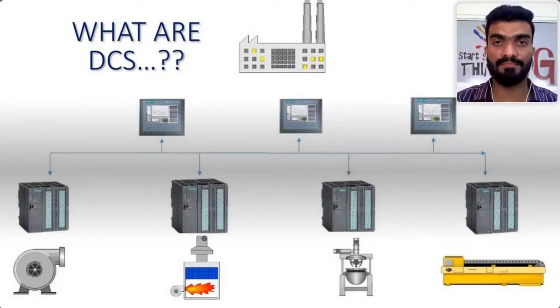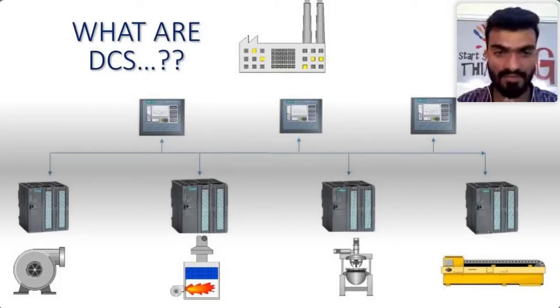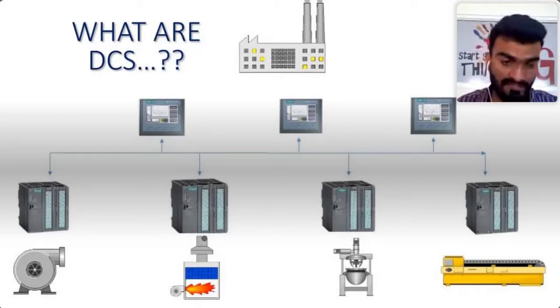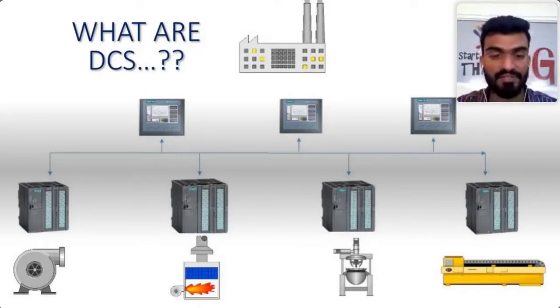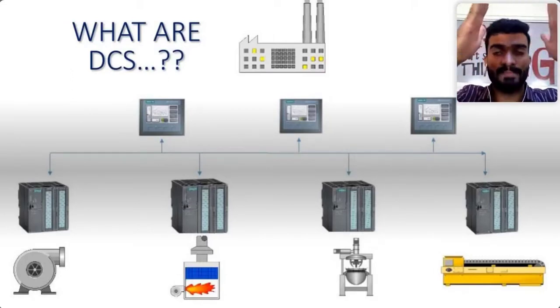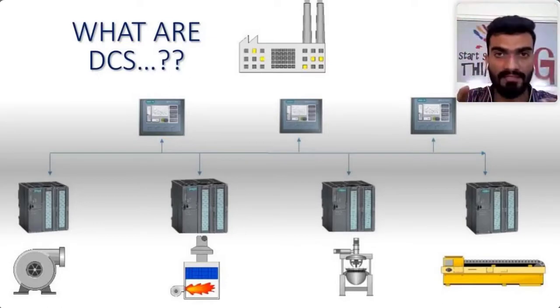In this slide we've shown three controllers, and the main distributed controls are all the bottom PLCs, second-line PLCs at different sections - say fans, furnace, machine conveyors - all these different kinds of PLCs at different sections are connected to the DCS. My DCS is going to drive the plant, monitor all the PLCs' data, and give the main data and controls to the management level or control room level.